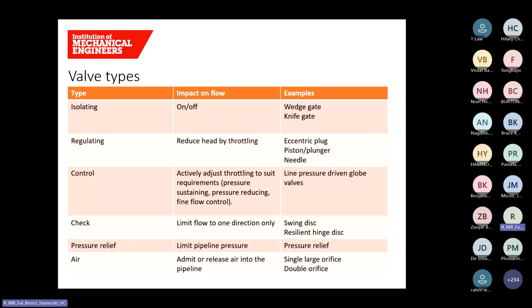I'll now briefly discuss the classification of valves that we use in the water industry. First of all, we use isolation valves, and these either allow flow to pass or prevent flow in a pipeline system. We use regulating valves, and these are used to throttle flow in a system. We use control valves, and these actively adjust to suit the system needs. So that might be pressure reducing or pressure sustaining. We use check valves to allow flow in one direction but prevent reverse flow. We use pressure relief valves, and these limit the system pressure to prevent over-pressurization of the system. We also use air valves, and these allow accumulated air to be released from the system or to allow air in and prevent negative pressure.